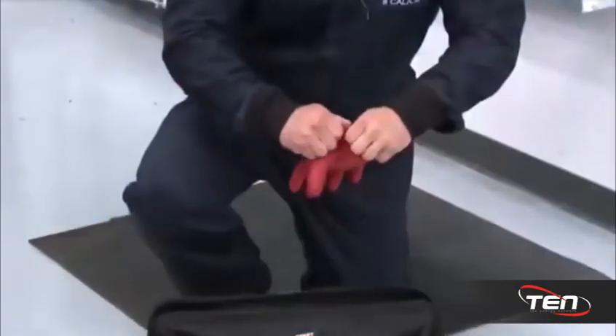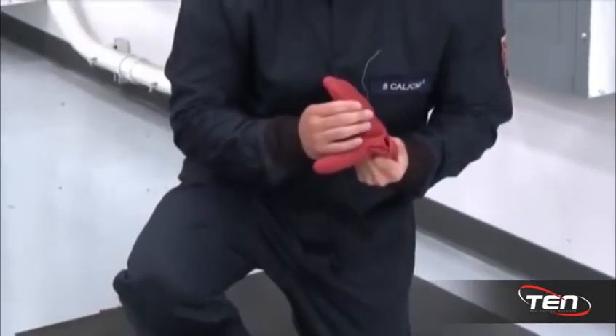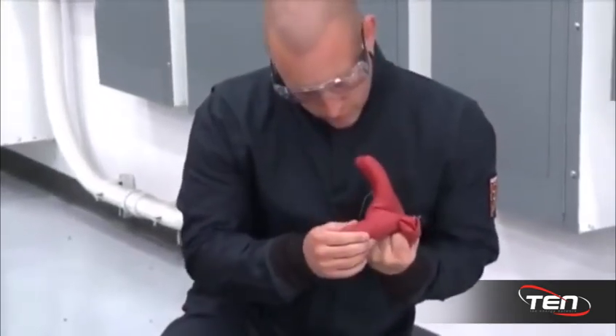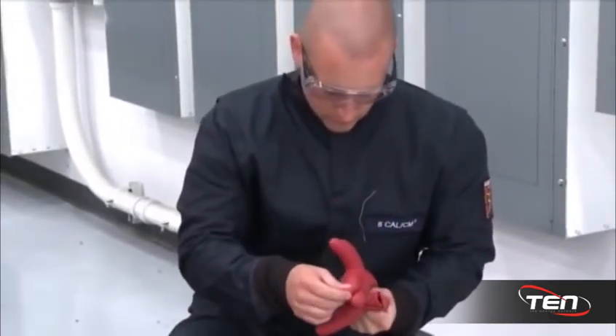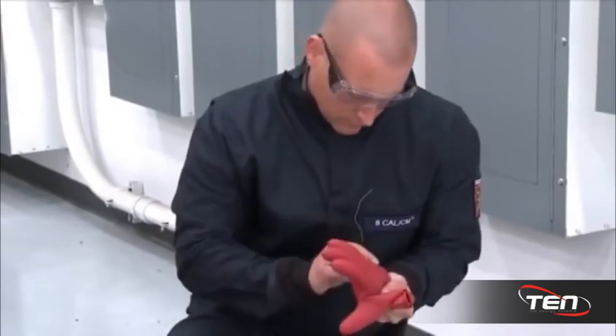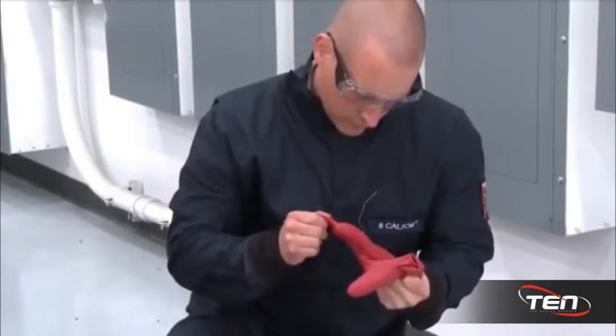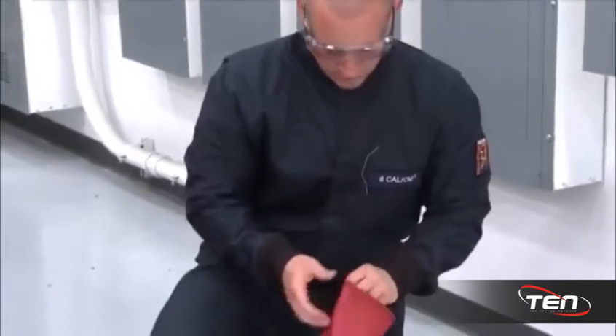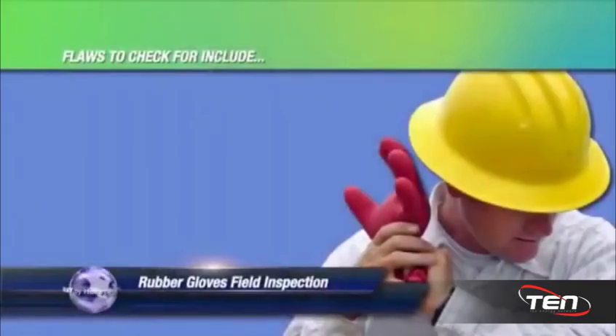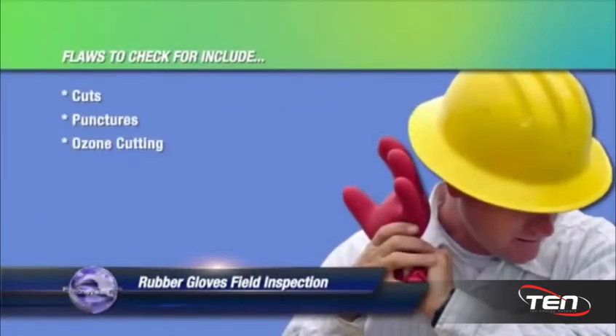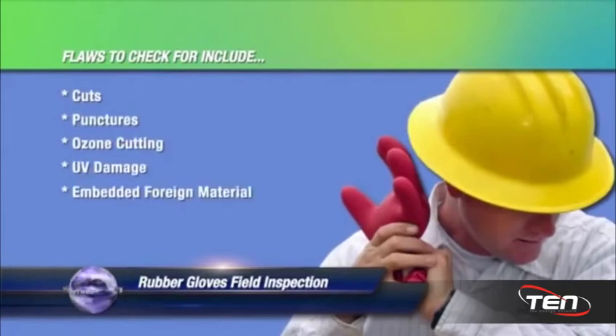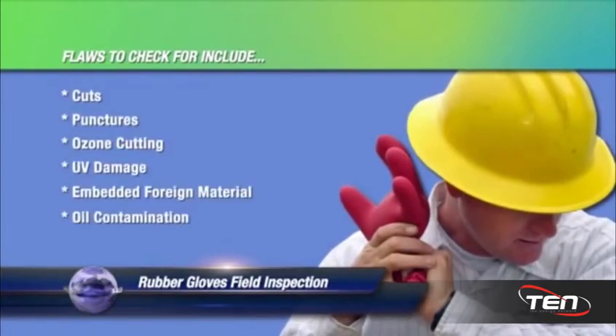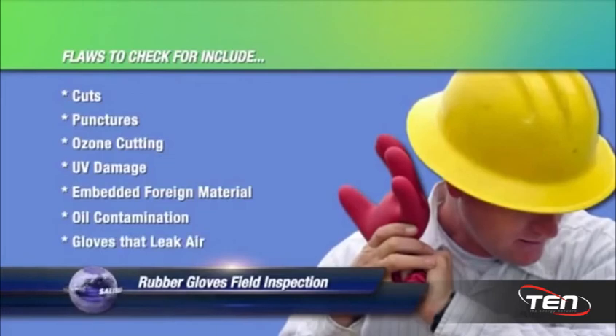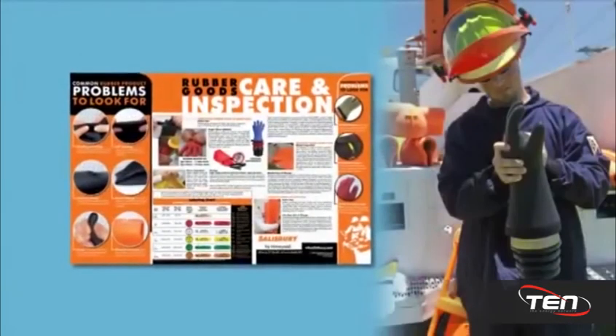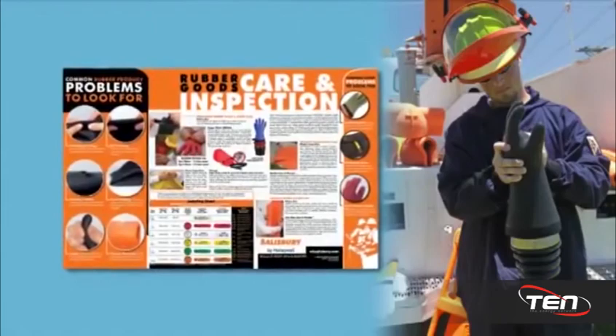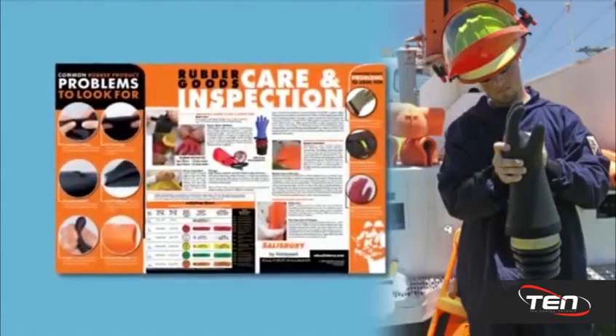Prior to each use, it is vital that you inspect your rubber gloves to make sure they are safe to use. Damage that has occurred to the gloves while in storage or during their last use could result in them being ineffective for protecting the user from electrical shock. The flaws you'll be checking for include cuts, punctures, ozone cutting, UV damage, embedded foreign material, oil contamination, or gloves that leak air when being inspected. Salisbury by Honeywell can help you understand and learn the inspection process to help ensure worker safety in the field.